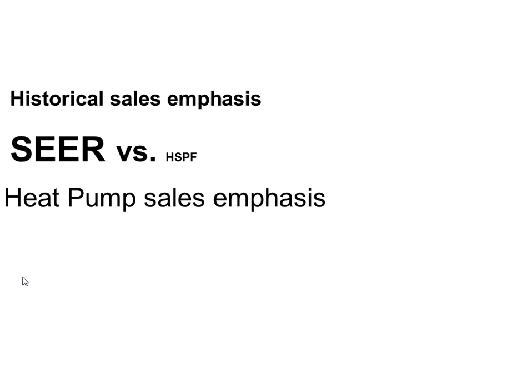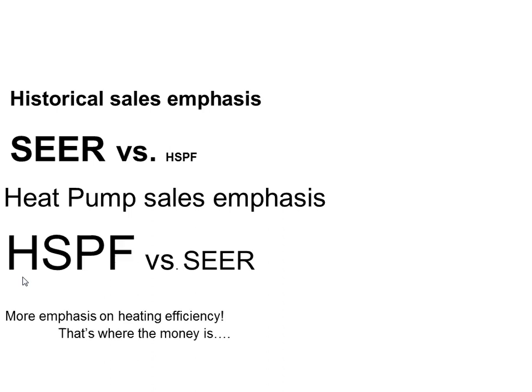Well, I shouldn't say that. There's a SEER rating for every heat pump, but it only applies to the cooling function of the heat pump. It has absolutely nothing to do with heating whatsoever. Every air source heat pump has a SEER rating and an HSPF rating. Both of these are AHRI published data. HSPF is the heating side, SEER is the cooling side.